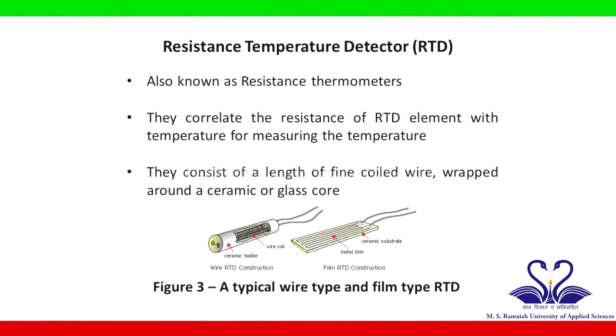A resistance temperature detector or RTD is a resistance thermometer which detects the correlation between the resistance of an element and the corresponding temperature. It is a length of fine coiled wire wrapped around a ceramic or glass core. An RTD can be of wire type or film type. Figure 3 shows a typical wire type and film type RTD element along with their parts.